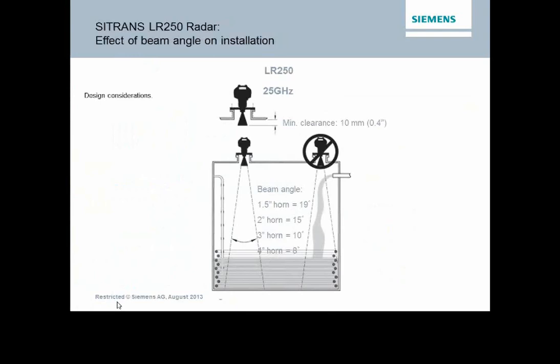So some of the key things we take a look at here in terms of design considerations is location. We're working with radar and ultrasonic, both have a beam angle. Over the years, this has been improved. We had to go with very large antennas in the past to try to get a small beam angle. When we take a look at your process, the larger the horn, the smaller the beam angle. The smaller the beam angle, the smaller the footprint.